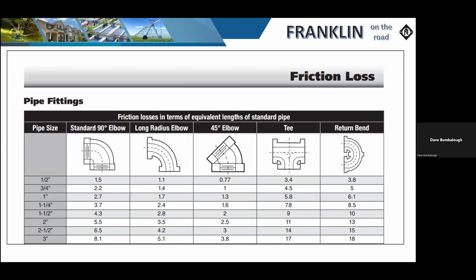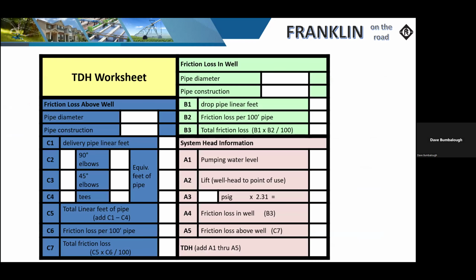So as we continue looking at friction losses, we also have to take into consideration our 90s, our T's, check valves. That all adds up, and as you can see here, they add up pretty quick. So a 1-inch 90 in this case is equivalent to 2.7 foot of head loss. Okay, so we want to make sure we take a look at that and add that in as well.